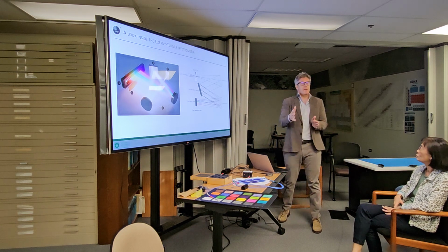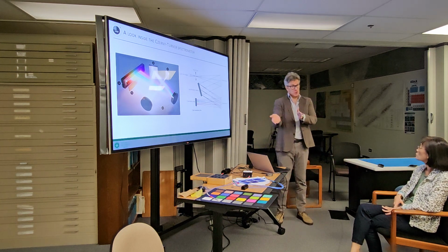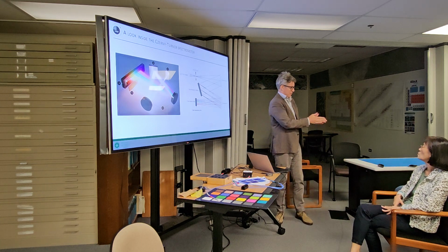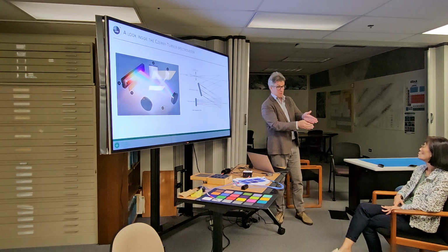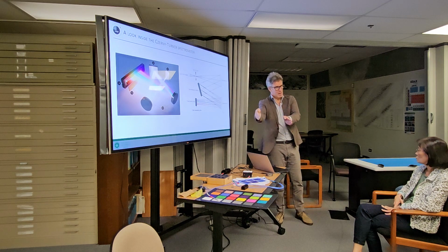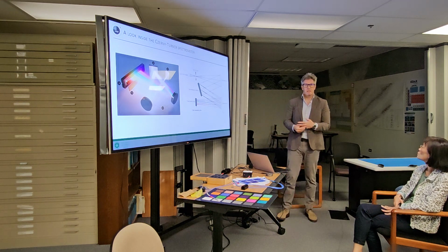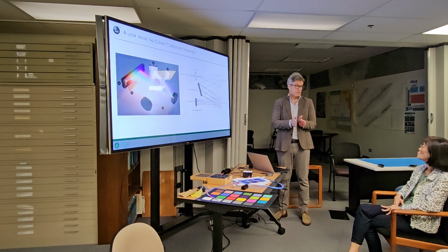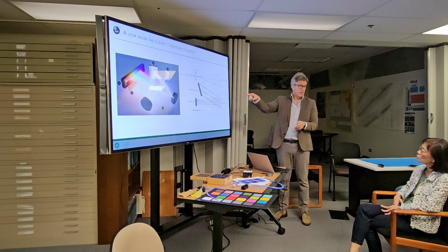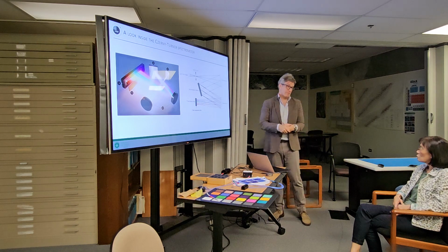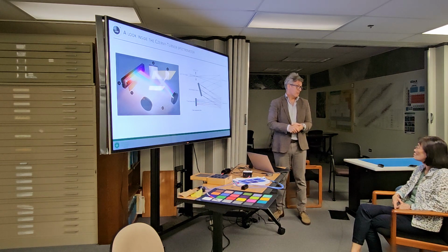So it's usually the long wavelength of one order overlaps with the short wavelength of the second order. Right. So you've got blue, green, red, and blue overlaps with the red, green, red. Now one way you can limit this order sorting effect is to look over a narrow wavelength interval. The broader the wavelength interval over which you diffract light, the stronger this order separating problem becomes. You get rid of it by using filters to throw away the wavelengths.